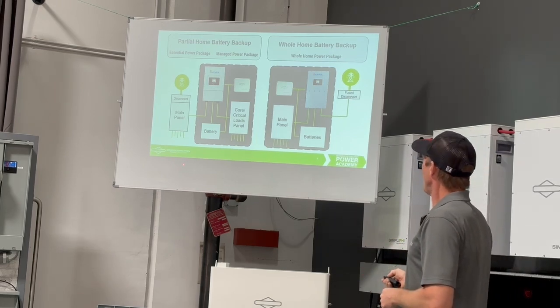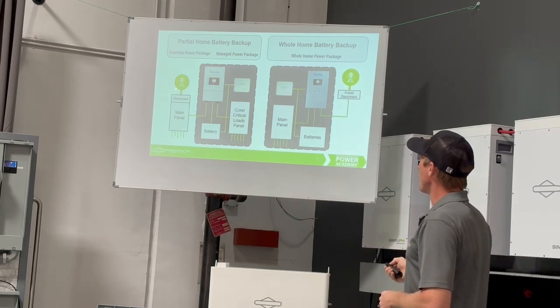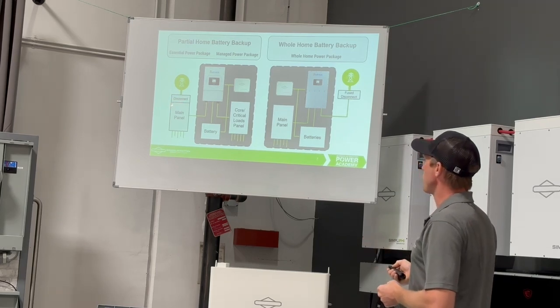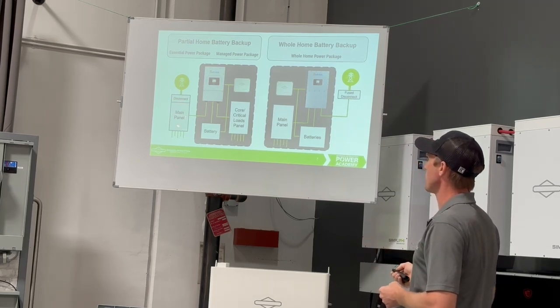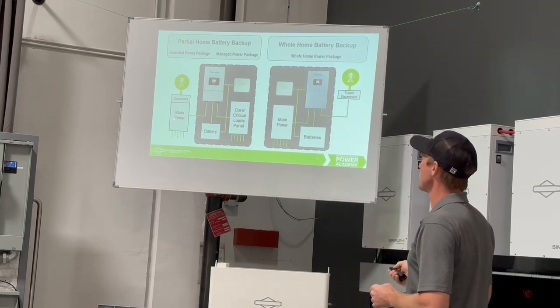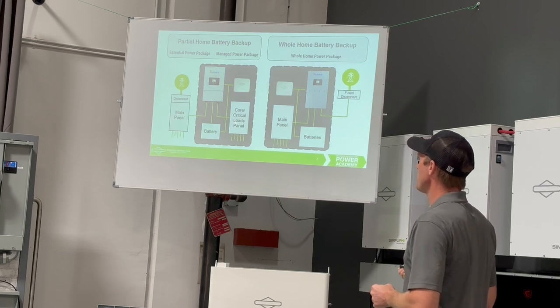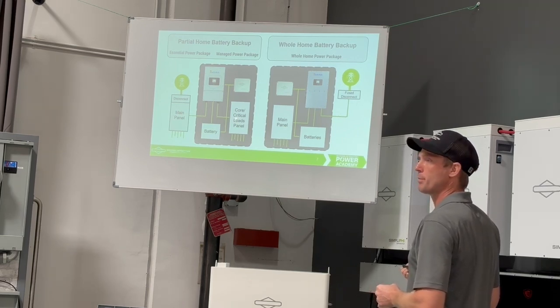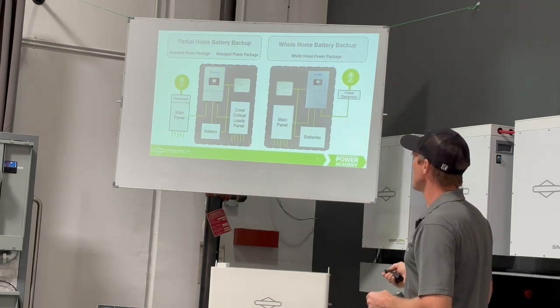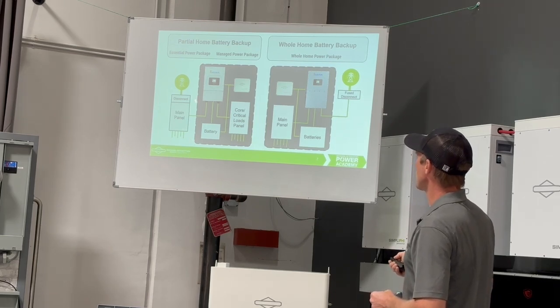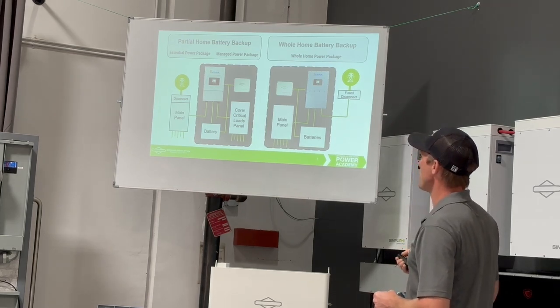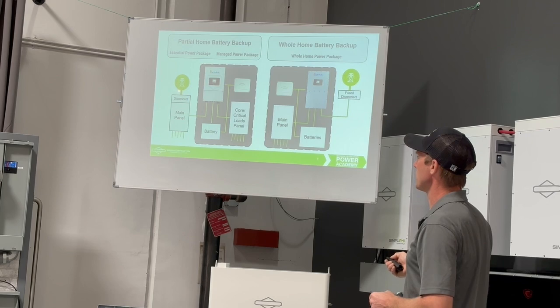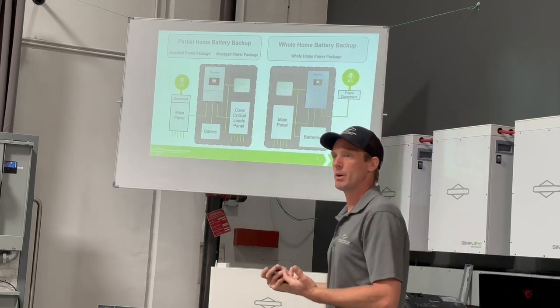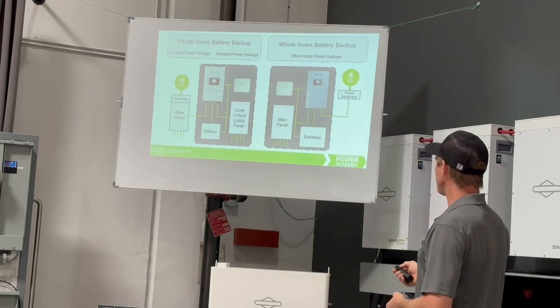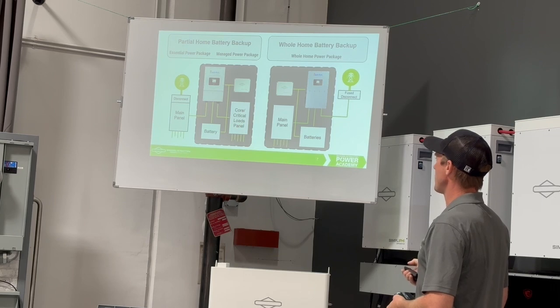Previously, with smaller inverters, you would have to pass through some of the panels. You'd take some of the loads out of the main panel, put them in a sub panel, and that sub panel would be backed up. So in a grid-down situation, the Sol-Ark isolates itself from the grid, so it's not sending any power back onto the lines that could hurt a lineman. And then it keeps alive this critical loads panel.